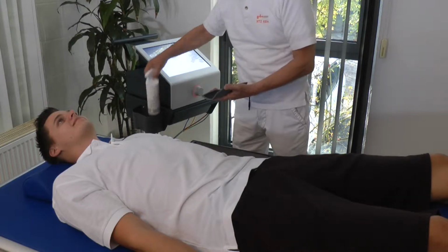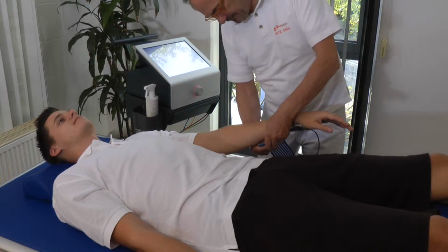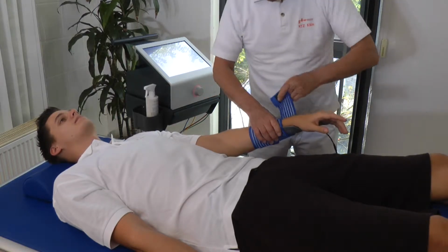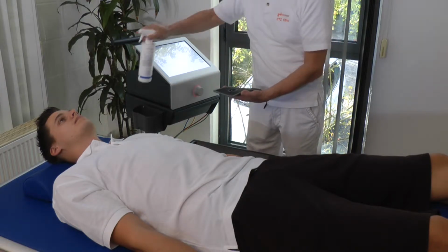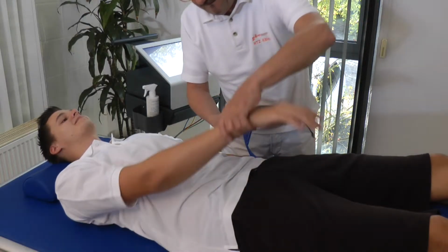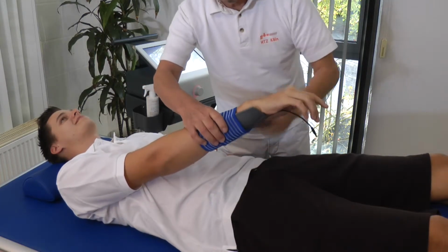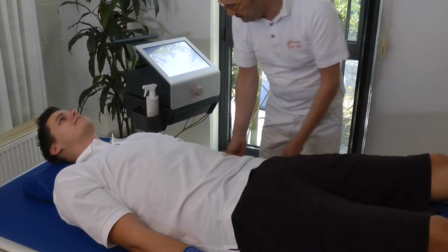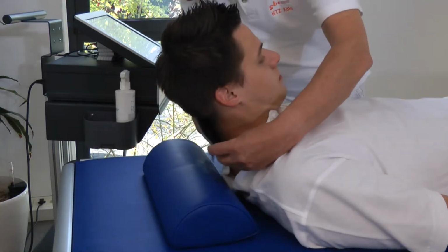The next 2 electrodes are placed on the 2 arms above the wrists. It is essential that the electrodes cover the skin completely. We do recommend to place 1 electrode in the patient's neck. However, this is optional. Yet, if you choose to take advantage of this electrode, just place it between neck pillow and neck.